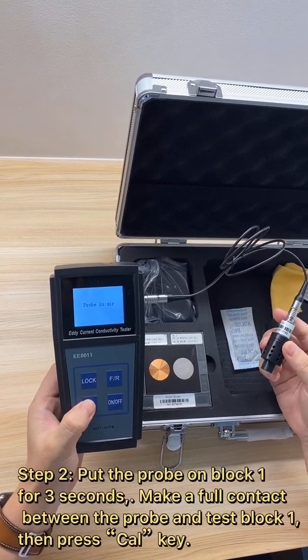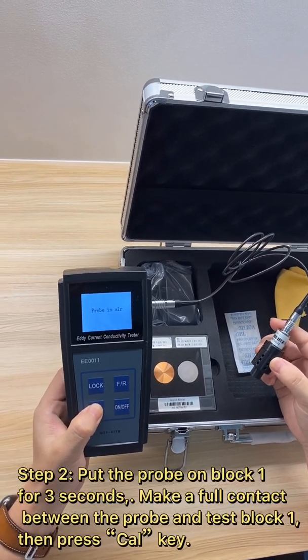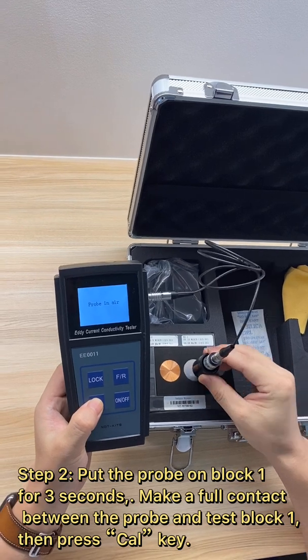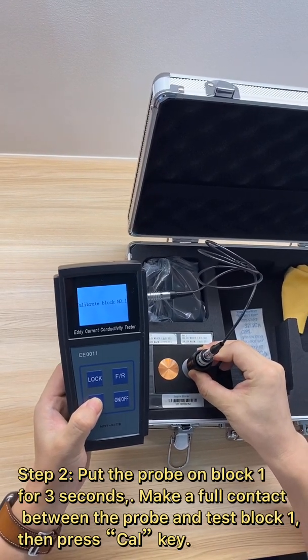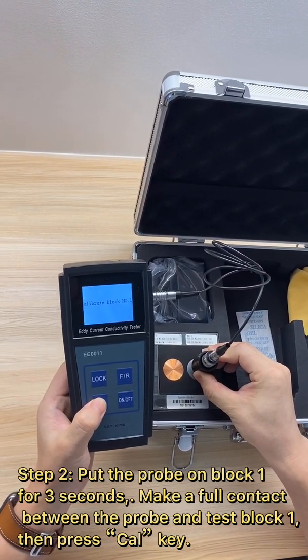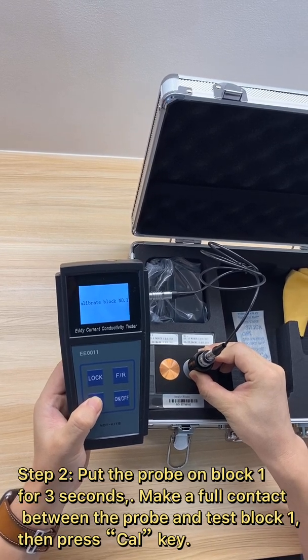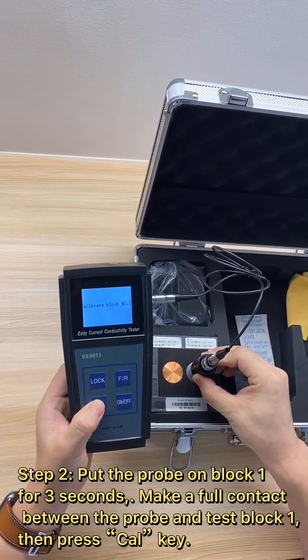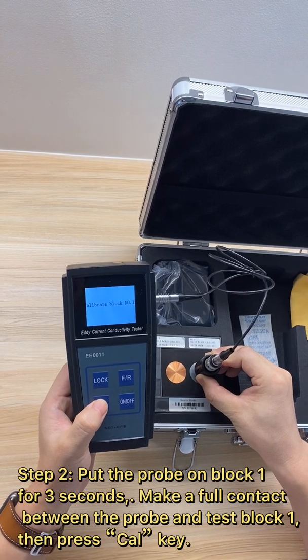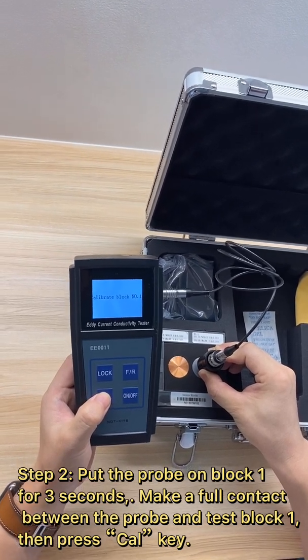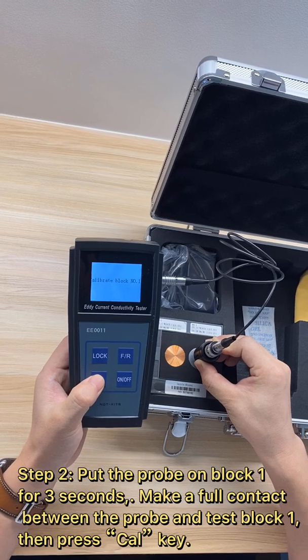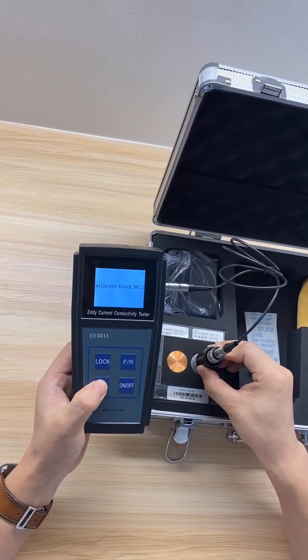Then put the probe on test block 1. Make full contact between the probe and test block 1 for 3 seconds, then press the calibration key to complete the calibration on test block 1.